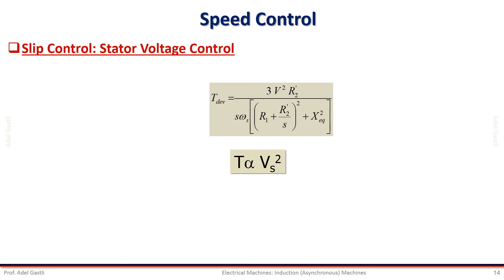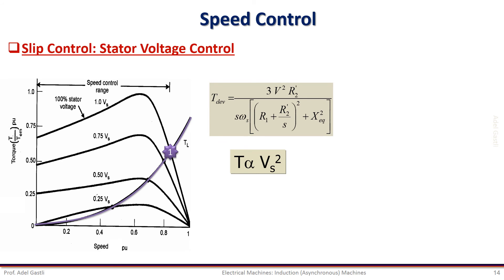In some applications, the speed of the induction motor can be controlled by varying just the stator voltage. Since the torque is proportional to the square of the voltage, the torque-speed characteristics take different shapes when the voltage is reduced. For instance, with a given load characteristic, the operating point will move from point 1 to point 2 if the stator voltage is decreased from V1 to 75% of V1. Notice that at point 2, the speed of the motor has decreased and thus the slip has increased.